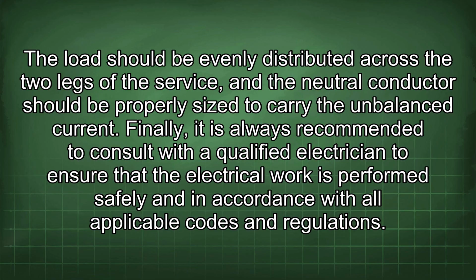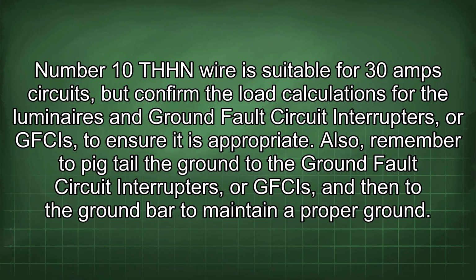Finally, it is always recommended to consult with a qualified electrician to ensure that the electrical work is performed safely and in accordance with all applicable codes and regulations. Number 10 THHN wire is suitable for 30 amp circuits, but confirm the load calculations for the luminaires and GFCIs to ensure it is appropriate. Also, remember to pigtail the ground to the GFCIs, and then to the ground bar to maintain a proper ground.